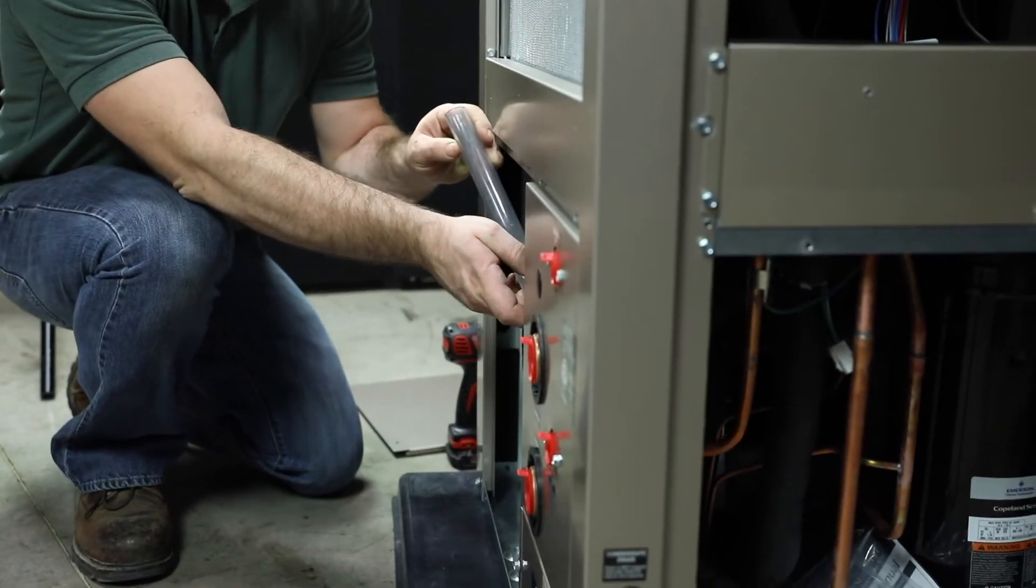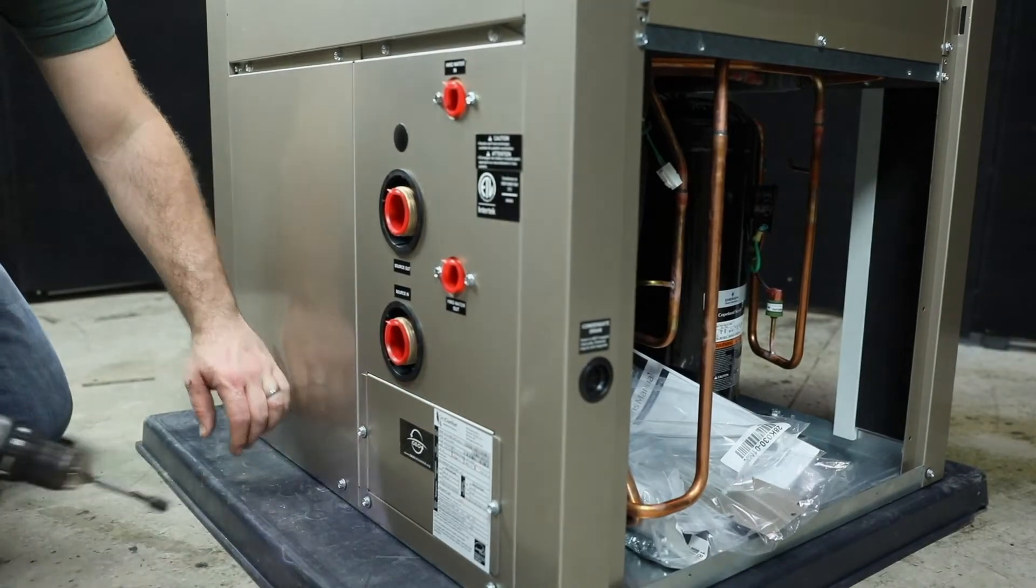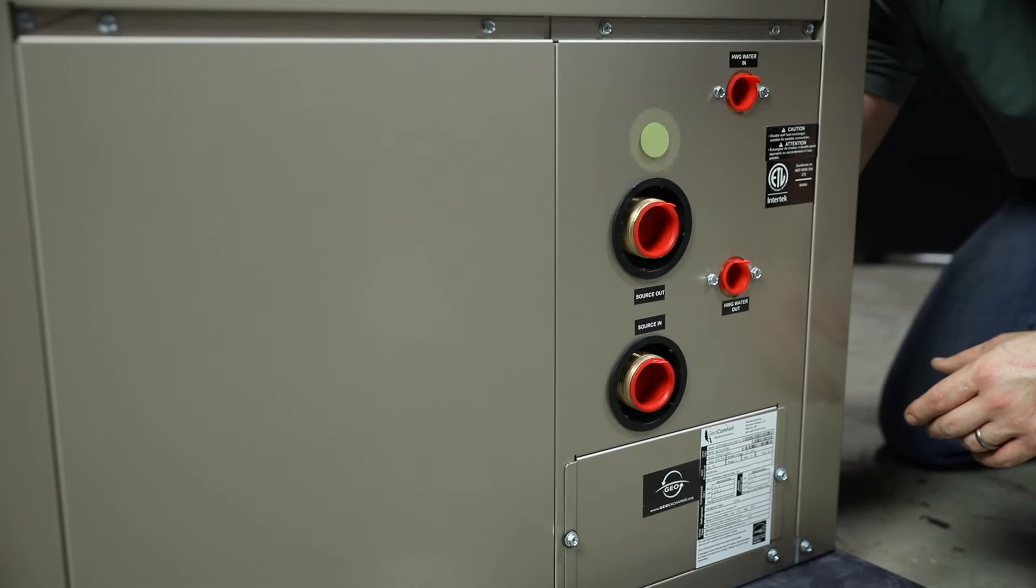With the condensate drain installed to the corner post, reinstall the lower left side rear panel. The pump kit will be installed onto this panel. Loosen and remove the small black plug above the water fittings. This opening will be used for the flow center conduit.